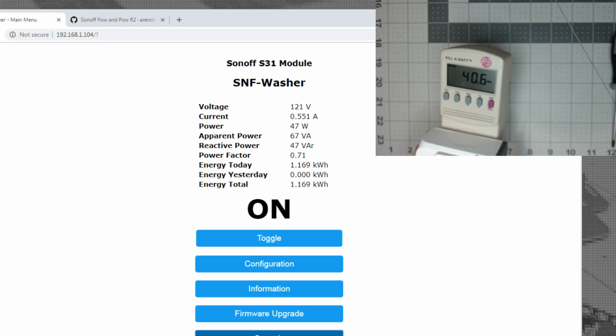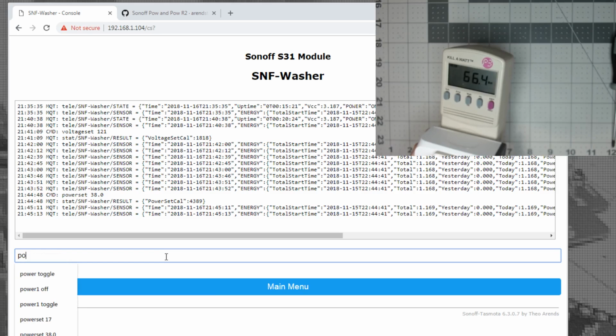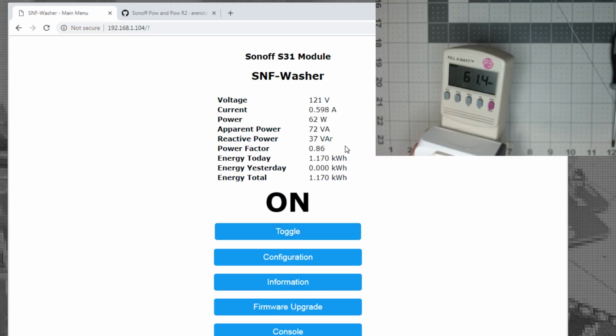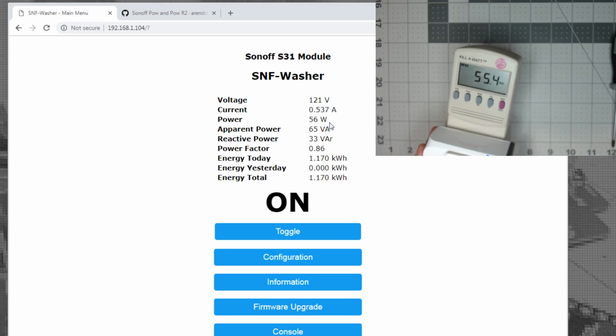So to fix that, we go to console and do it again. Power set 64. See if we got there. 62, 61, which is pretty close, so we should be good enough. Once you've got this reading matching in your wattage and your voltage, the calibration's done.